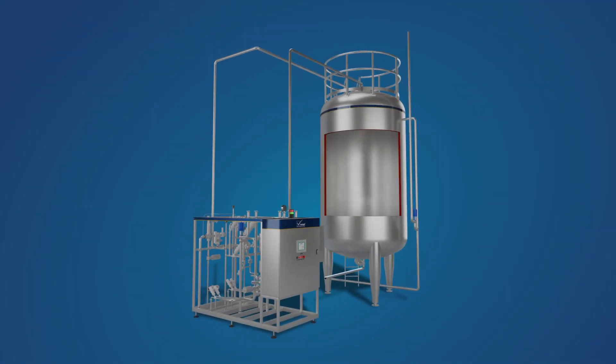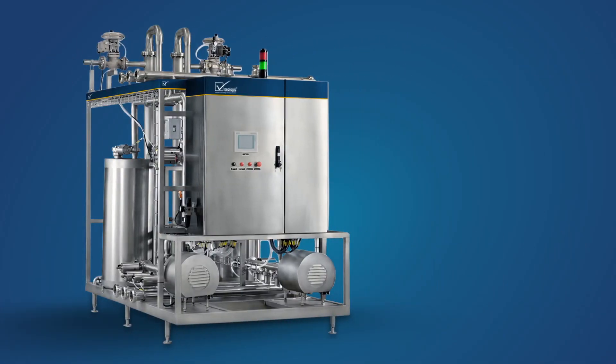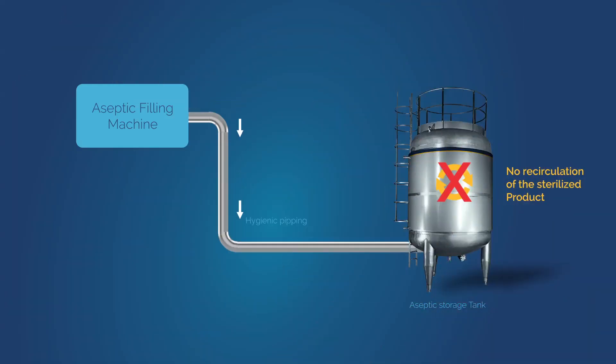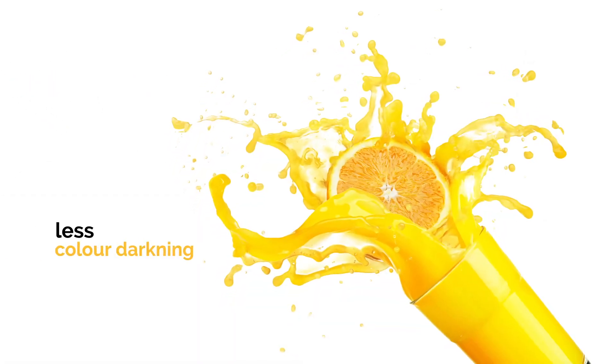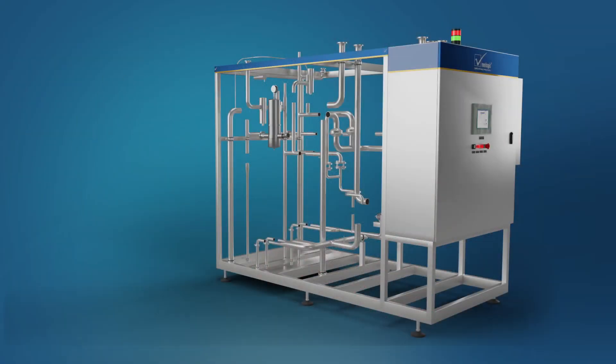Sterile air supply to the tank automatically controls the feed pressure required for the aseptic filling machine, which ensures no short stops for the filling machine operation. The aseptic storage system comes with a dedicated CIP module to clean the entire system. Since there is no recirculation of the sterilized product to the filling machine, there is a vast improvement in quality of product in terms of less color darkening and loss of flavor.